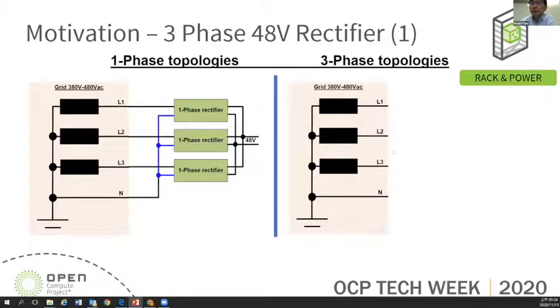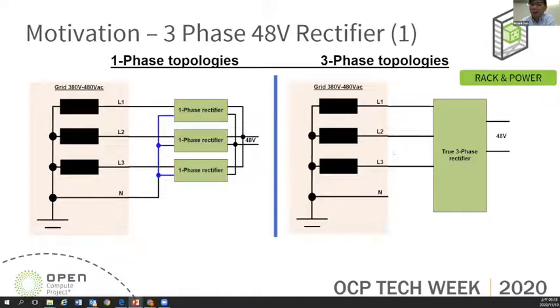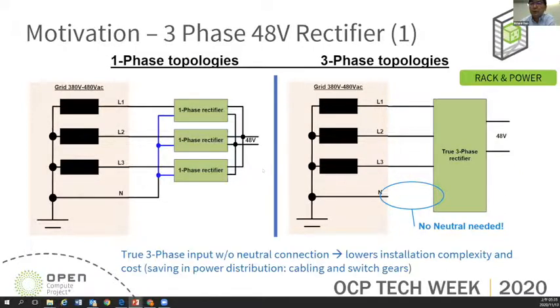Then when we do the 3-phase rectifier design, we can select the suitable number of rectifiers based on the power demand. It does not need to be a multiple of 3. So it's also good for increasing the power density. One of the benefits we can have is that if we use this kind of 3-phase design, we don't have the neutral connection. So we can save some of the infrastructure cable and switchgear cost. But if we want to do the similar thing in single phase, it is not easy to achieve.